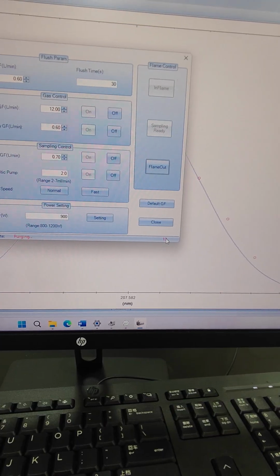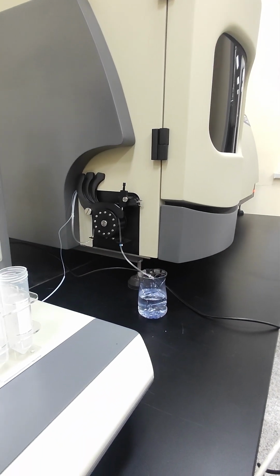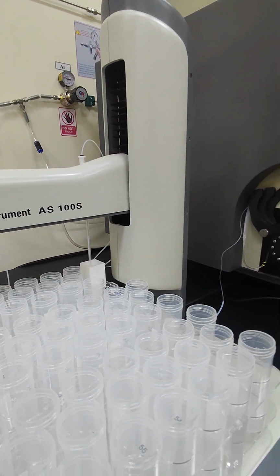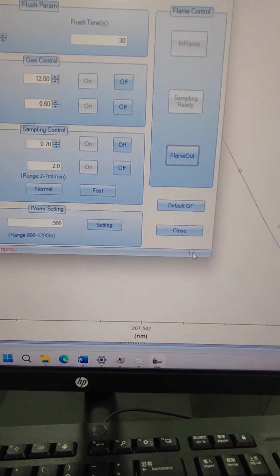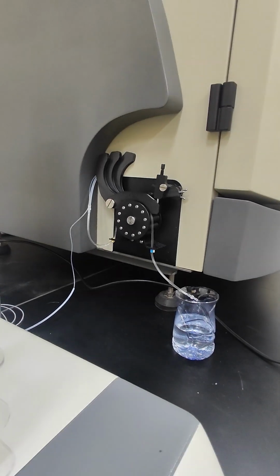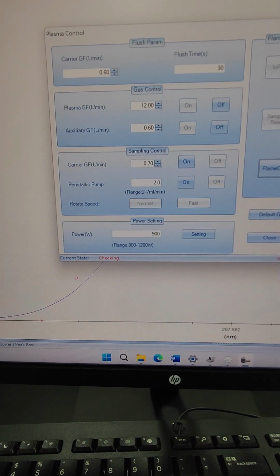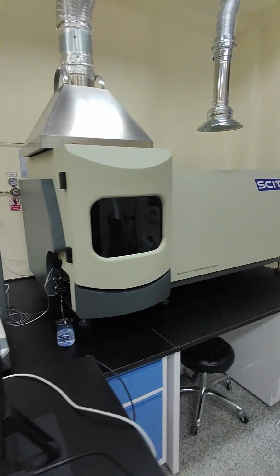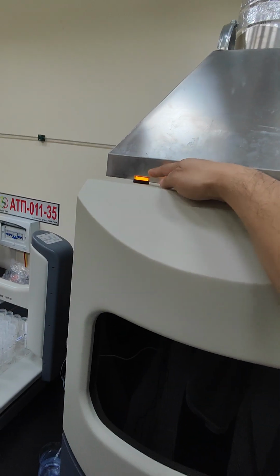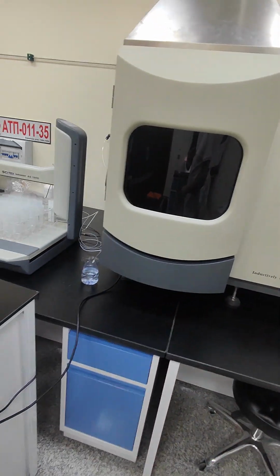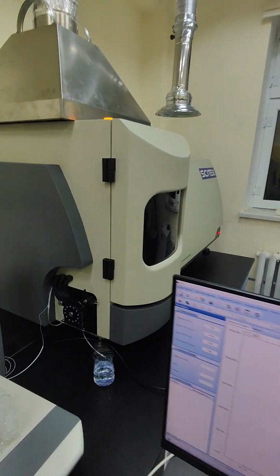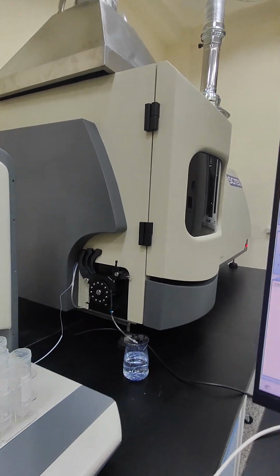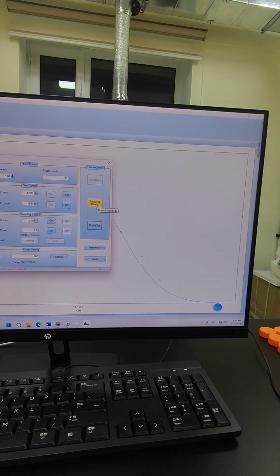During this condition, it will keep running and sampling the water inside. When the timer goes to 0, the waste pump will stop, and it will go to checking, and later it will go to flame on. You can see it's flame on now, and on the top this indicator will turn on. After the flame has been on for about 7 seconds, press sampling ready.